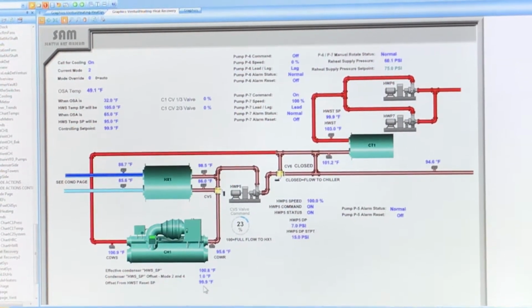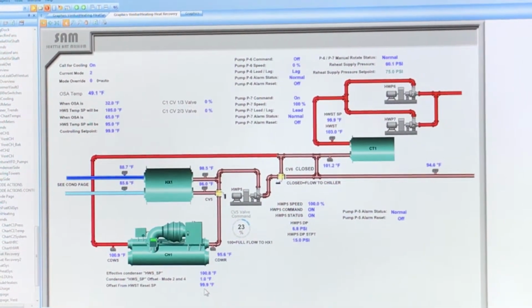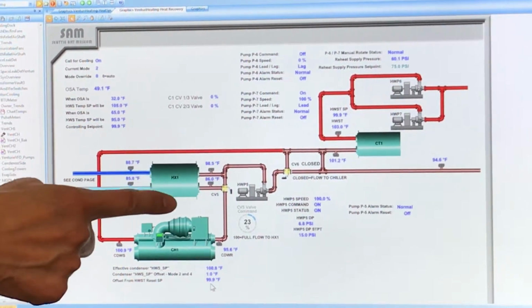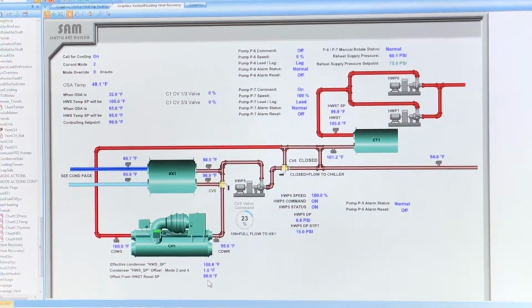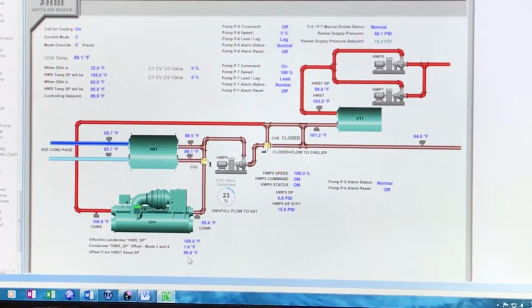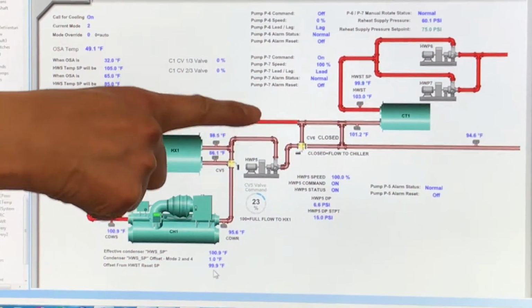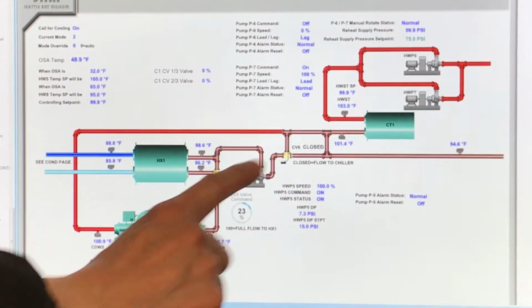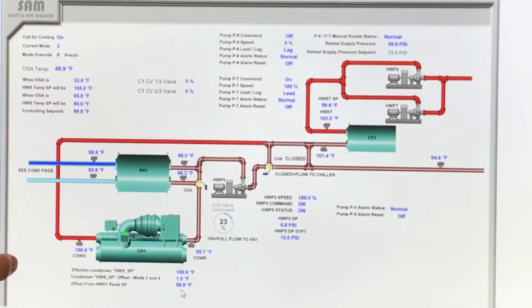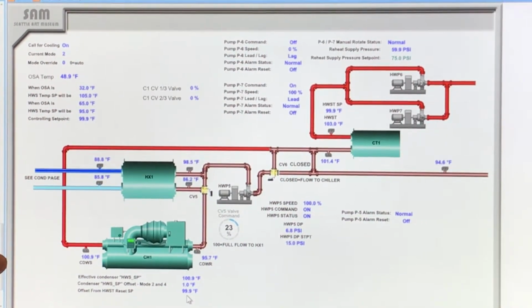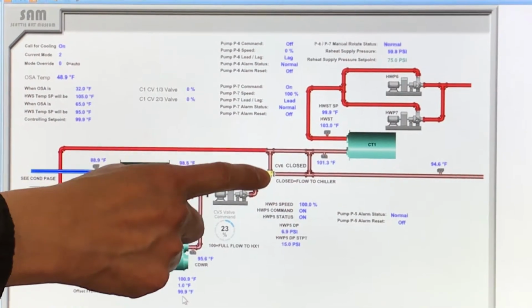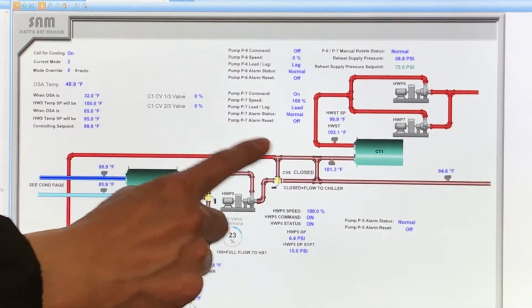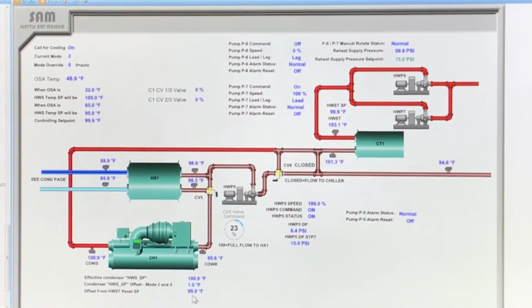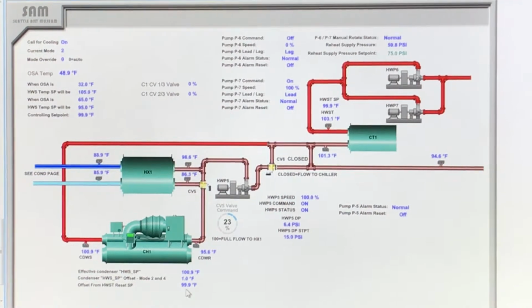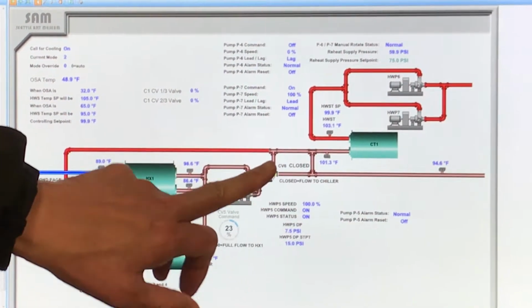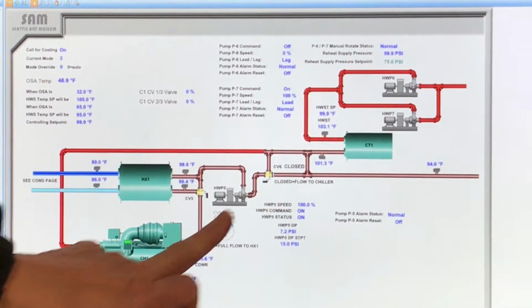It likes a load. When you are in mode 3, this guy will not be running. When you are in mode 4, this guy will be running like mode 2, because you are doing the heating loop. When you are running in mode 5, it will be different. This will be closed, so the water will be going through here because you're running this chiller in cooling mode. Mode 6 also, this guy will be closed, this will be closed, and you are only running water through there and through the heat exchanger. So that's what this guy is doing. When you're delivering hot water to a system, this will be closed, and when you're doing the cooling only mode, this will be closed.